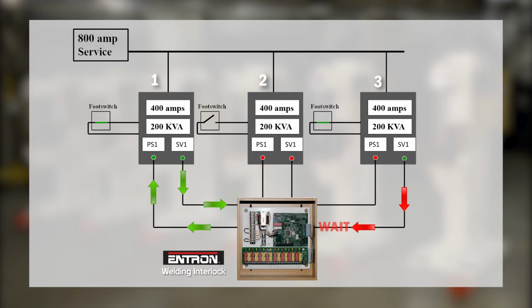The pressure switch for machine 3 won't make until SV1 from machine 1 is removed from the interlock. Machine 2 is initiated and requests permission to fire. The pressure switch for machine 2 won't make until SV1 from machine 3 turns off.